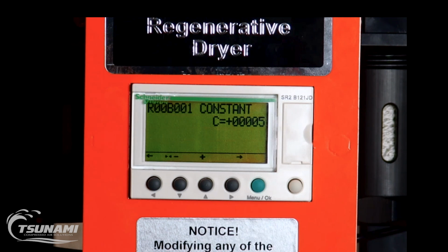And what that does is provide energy efficiency for an air system if the dryer's plumbed between the compressor and the receiver tank, or if we have a dryer tied into a piece of equipment. And if that equipment's not running, the dryer doesn't necessarily have to be drying air, because it will constantly sweep air if we don't have it in some form of pause mode. So to really maximize energy efficiency, if there's a signal available that we can access on the equipment or off the compressor to send to this PLC, we then can make this dryer even more energy efficient.